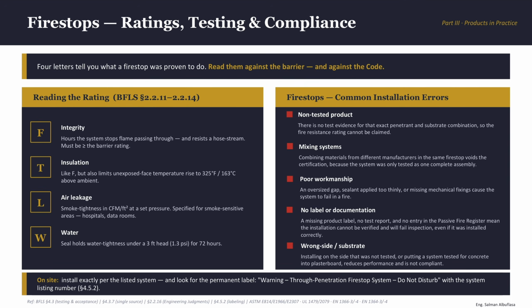These are the most common installation errors. Most fire stop failures on site are not because someone used a bad product, as we said before. It's because they used a good product, a certified product, and installed it wrong. So a correct product installed incorrectly gives you zero protection. Doesn't matter. First, using a product that was not tested for that situation. If there is no evidence for that exact penetrant and the exact substrate, the rating cannot simply be claimed. It may look identical, it may look the same, but it doesn't matter. If it was not tested for that configuration, it is not rated for that configuration.